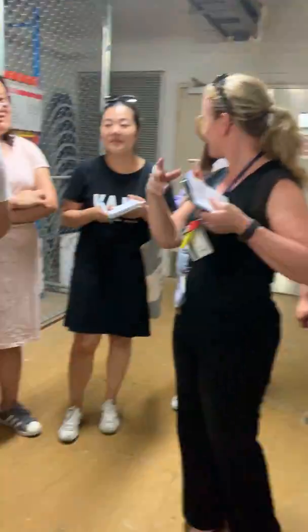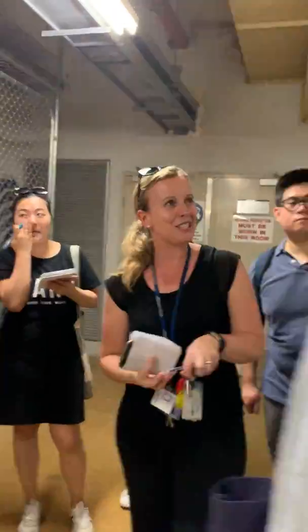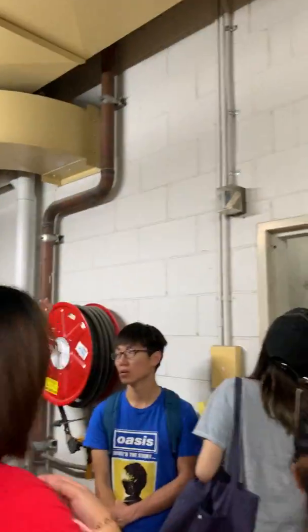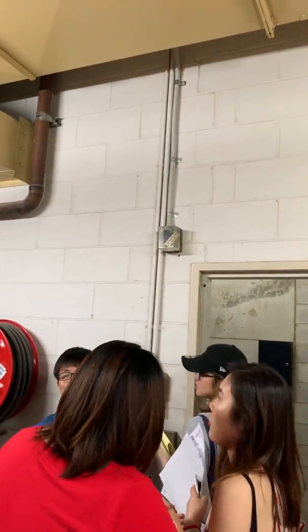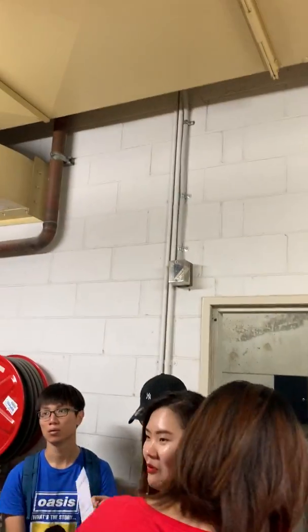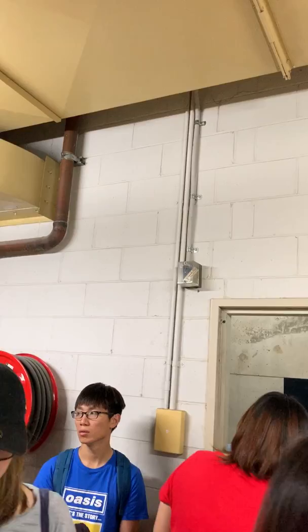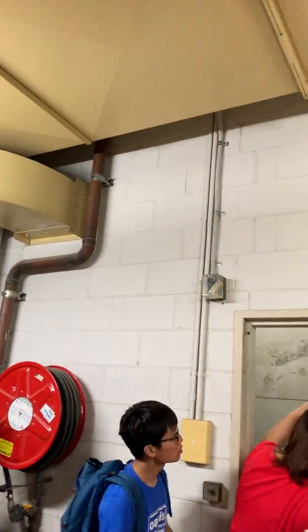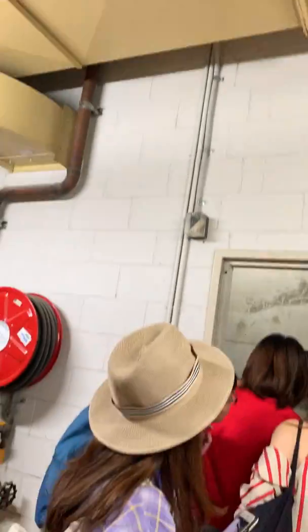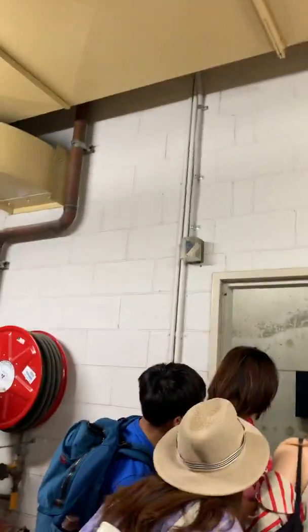Is located up there. So they've had to think about how do we get this motor out when it needs replacement. Not really an accessible space to bring in a crane and some lifting work, so they will use that steel bar. It has 3T written on it, so it's got a 3-ton weight limit. And they will use that as a hoisting mechanism. So you put a cable over the top of it and they can lift up the motor, put the motor onto a trolley, be able to wheel out. So they had to plan for that. Not an easily accessible location.